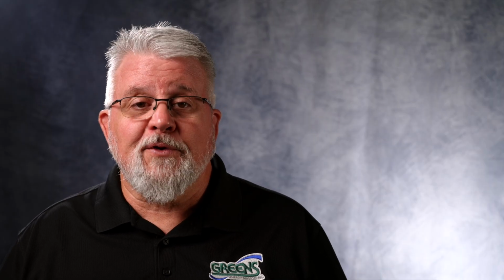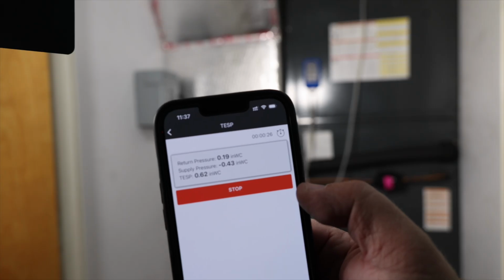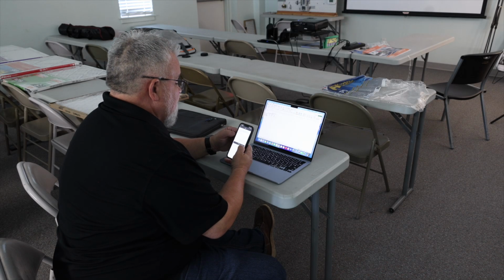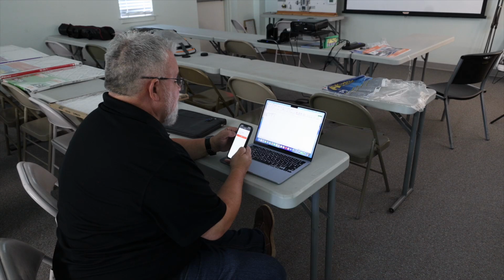Your system has to pull air through that filter every time it runs. And the more restrictive that filter is, the harder your system has to work. Think of it like breathing. A basic filter is like breathing normally, but a high filtration filter can be like trying to breathe through a thick blanket. So instead of just guessing which filter is best, we're going to measure it. We're running a static pressure test on every single one of these filters to see exactly how much resistance each one adds to the system.